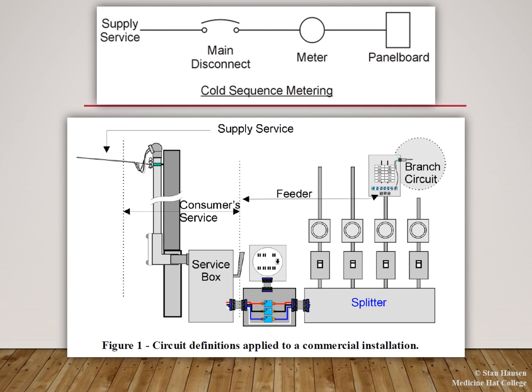Rule 6.402 sub-rule 2 states two different conditions. The first condition is if the service is over 200 amps, we need to use cold sequence metering. The second condition is if it is over 300 volts, we also need to use cold sequence metering. The idea behind this is that the incident energy, if the voltage is sufficiently high or the current is sufficiently high, is dangerous enough that people can get seriously hurt by working on live equipment. So therefore, they restrict the use of live equipment as much as possible.